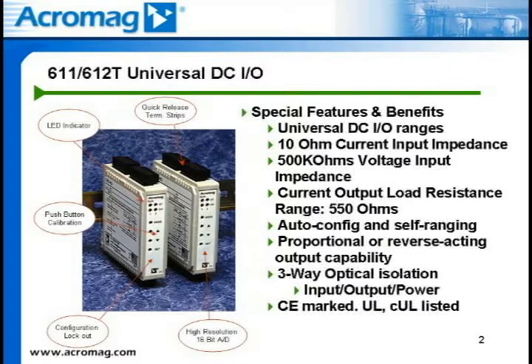The 611T and 612T isolated transmitters are designed to fit applications where three-way isolation is required. Three-way isolation refers to isolation between input, output, and power. The module is also designed to meet the stringent approvals of being CE marked and UL and CUL listed. Other special features and benefits include quick release terminal blocks for easy installation, LED indication for power, operation, and configuration status, configuration lockout capability, and a high-resolution 16-bit A to D for high accuracy of better than 0.1% of span and reliability.